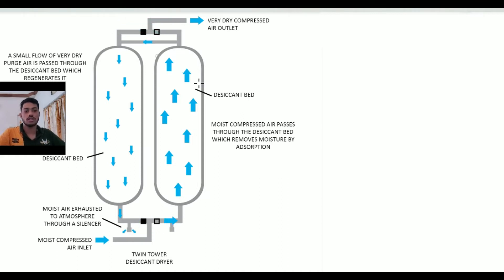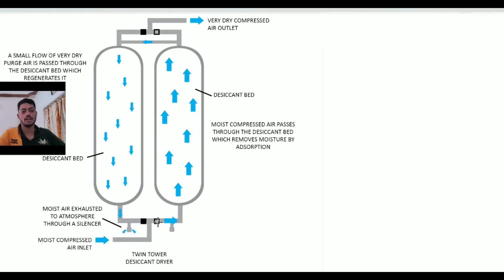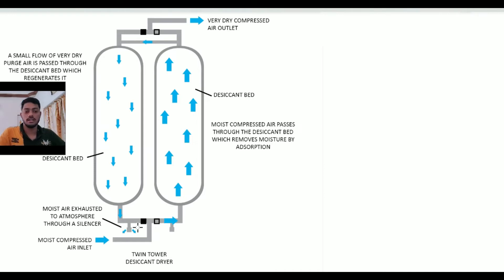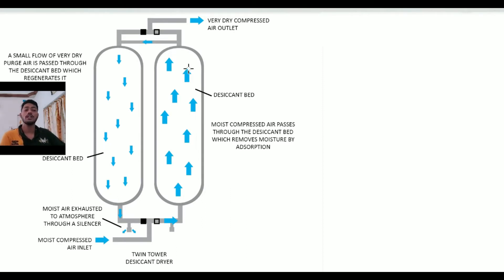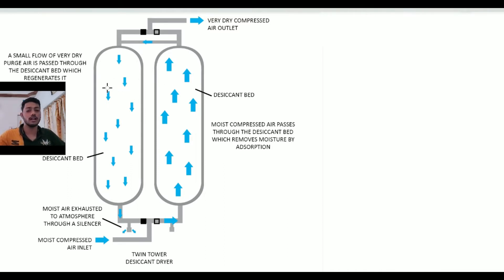They are pneumatic or in small desiccant dryers, solenoid valves are used. When the cylinder is drying air, that cylinder is called the online cylinder or processing cylinder, and the other one is called the offline cylinder or regeneration cylinder.